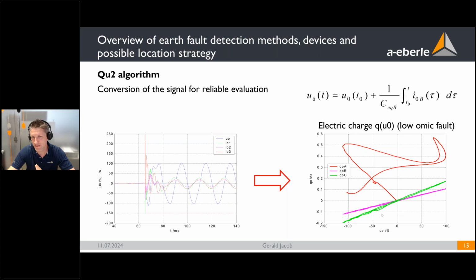As you can see, there are 3 different lines. In this example, the first feeder A is the affected line, and B and C are the healthy feeders. The healthy feeders end up with a straight line with a positive gradient, and the affected line in the beginning also has a straight line, but with a negative gradient. Then it gets a bit weird, some kind of rotation. For very high ohmic faults, this line is quite short, so there's another criteria for very high ohmic faults that can be used to calculate this rotation.